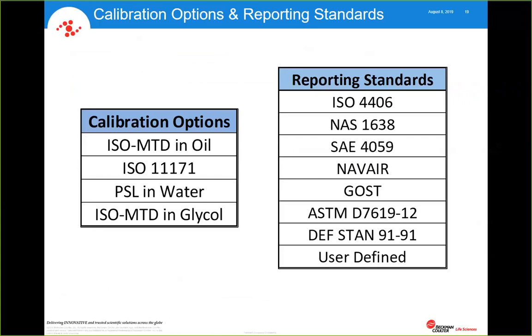Calibration option reporting standards. With an MTD calibration, you have ISO MTD in oil, the ISO 11171, the PSL in water calibration, and then also the ISO medium test dust in glycol. With the MTD calibration or the 11171 calibrations, you have the full suite of reporting standards on the right: the ISO, the NAS, SAE, NAVAIR, GOST, ASTM, et cetera. So when you have a medium test dust cal or an 11171 cal, you can report out to all of those standards.